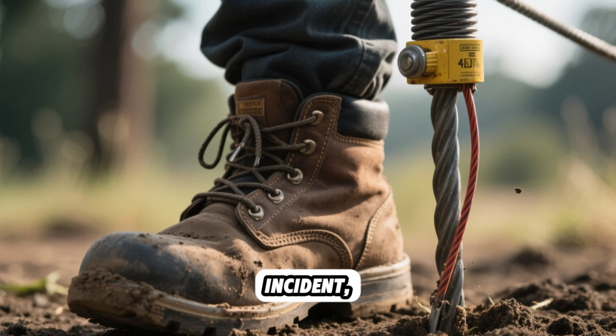This story highlights a critical concept: induced voltage. Even when a line is confirmed to be de-energized and disconnected from the grid, it can still be incredibly dangerous. Nearby energized lines can induce a voltage onto a dead line, much like a wireless charger powers your phone. This ghost voltage can be more than enough to be lethal. Without grounds, a lineman touching that line would complete the circuit and the induced current would flow right through them.